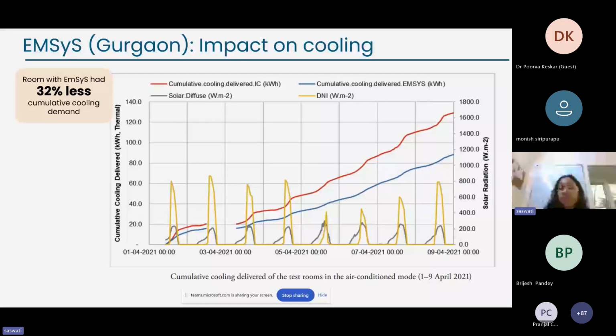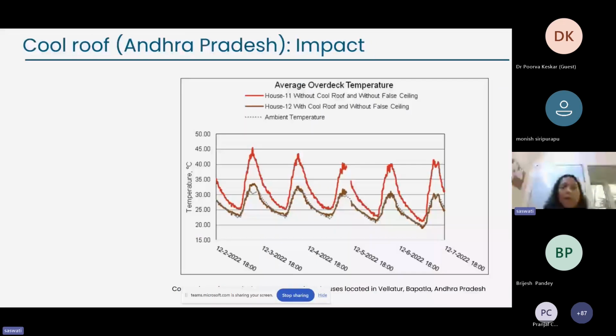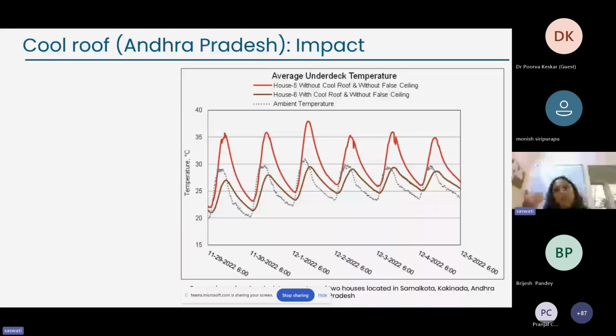Another passive strategy, the impact of which I'll show you through monitored results, is cool roof. This is a test we did in Andhra Pradesh over many affordable housing projects, small residential projects. Here you would see with and without cool roof, the overdeck, meaning the outside surface temperature of the roof, is 10 to 12 degrees Celsius cooler with the cool roof. The underdeck temperature, meaning the temperature of the inside surface of the roof facing the room, which would actually have more impact on the comfort of the person sitting inside, was found to be 6 to 9 degrees Celsius cooler with a cool roof.